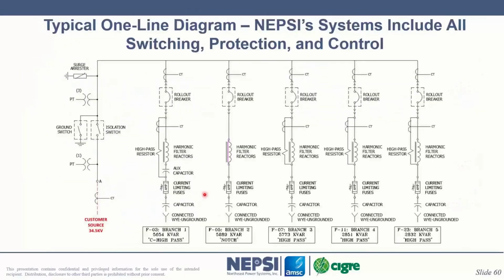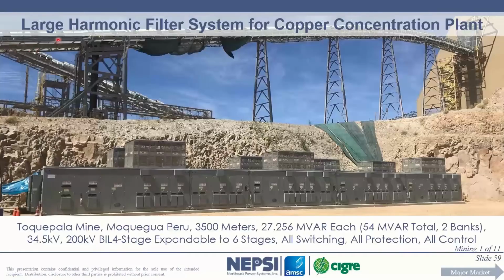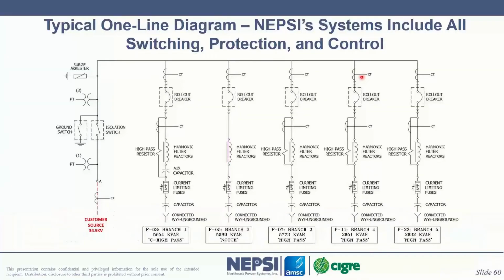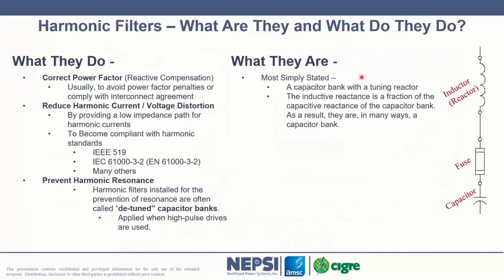I have a large mine system as we show it here. You can see here this is a conveyor system, but mine projects have crushing mills, grinding mills in them. They use cycloconverters, large VFD drives, cycloconverters sometimes on the order of 25 to 30 megawatts in power consumption, producing a significant amount of nonlinear load. We're chopping up current, we're creating harmonics, and you don't want that harmonic current to flow out into the network. So what do we do? We put a filter system in to pull that harmonic current from the power system at the mine, so that it doesn't flow out into the network and pollute the network. So that's oftentimes the purpose of a harmonic filter.